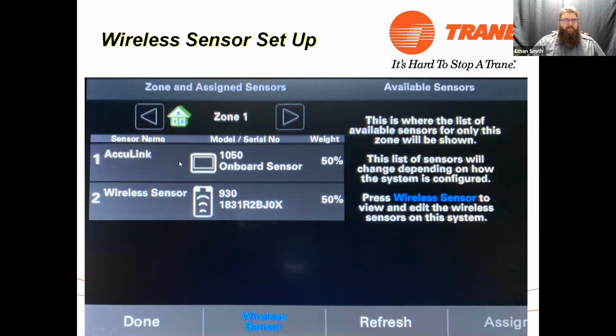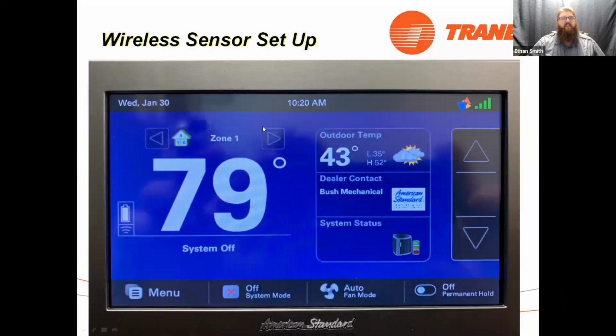Now, if I didn't want to sense temperature from the 1050, I just wanted to sense temperature from the 930, I could click on this 1050 sensor and it would give me the option to unassign that 1050 sensor from zone 1. Okay. So once your zone sensors are assigned, you can then exit the installer setup. You go back there, you notice we've got zone 1, and that wireless sensor shows up with a wireless signal and a battery life indicator on the 1050. Okay, so it's going to be pretty important that you do that before you exit the installer setup. Otherwise, you get to go back through the zoning system setup. The nice thing about the zoning setup is once you've gone through it once, it retains all of your settings, so you can use those manual selections just to make it go faster.